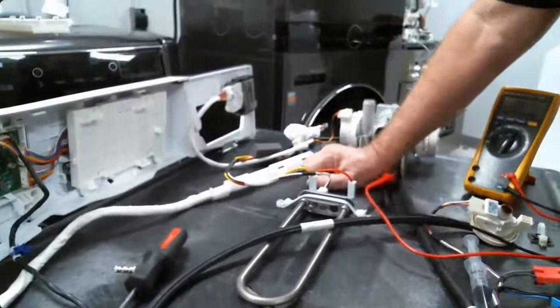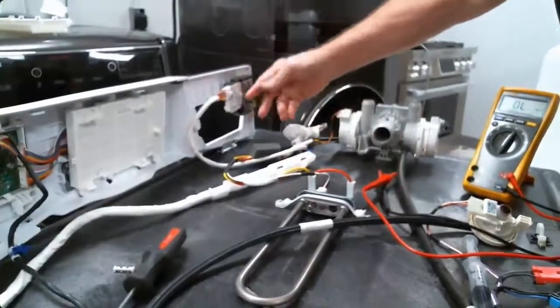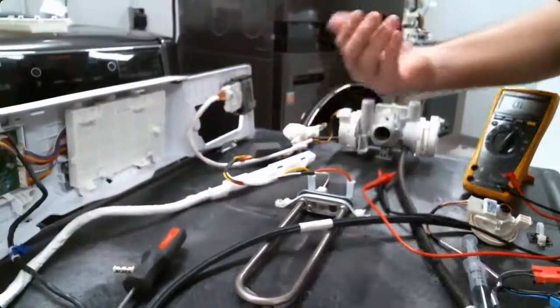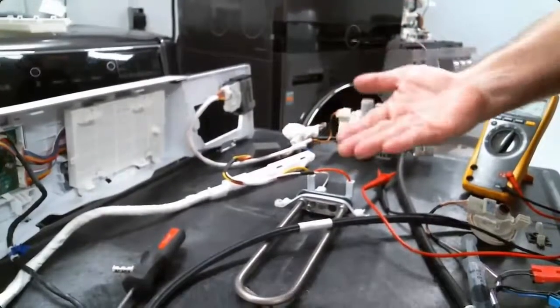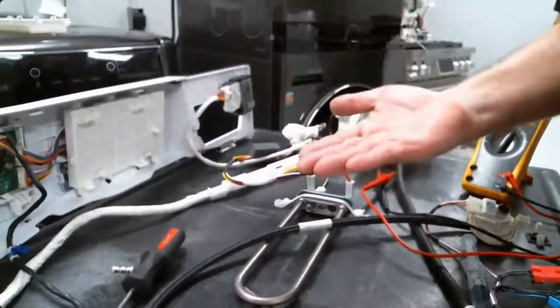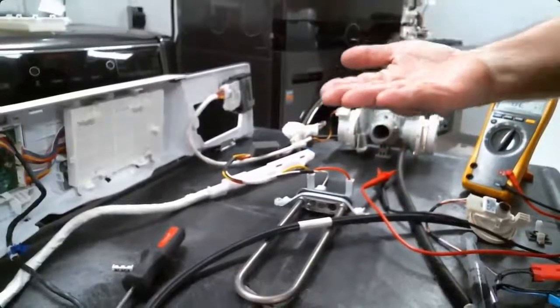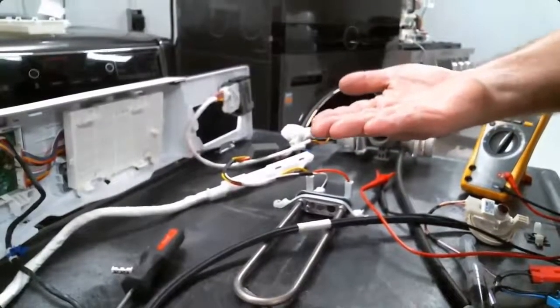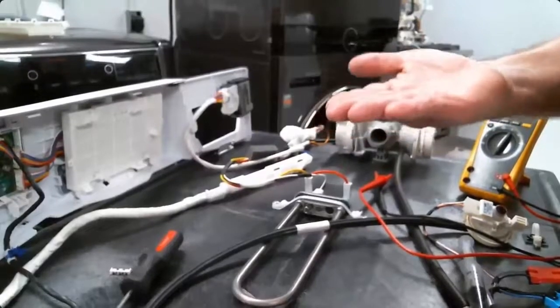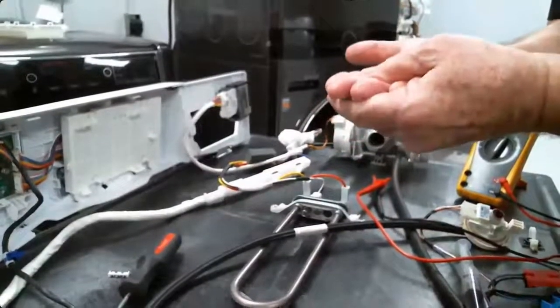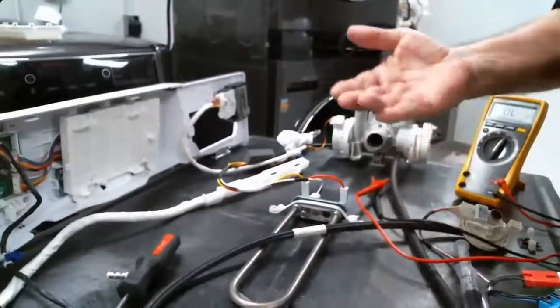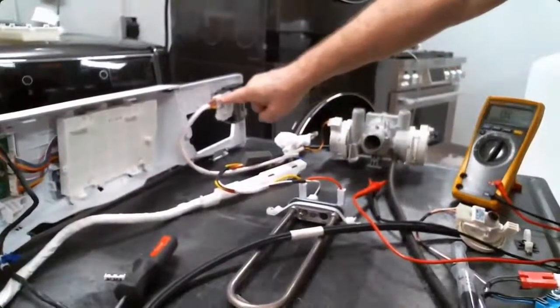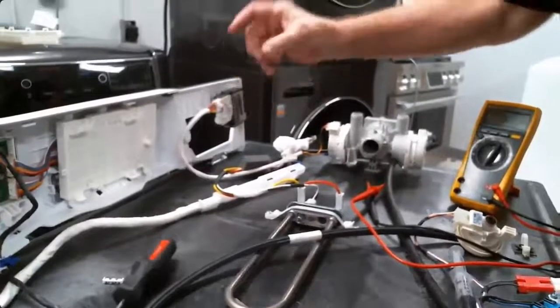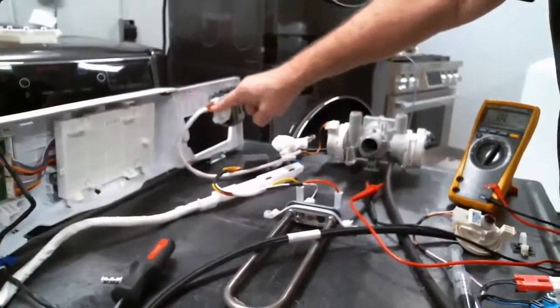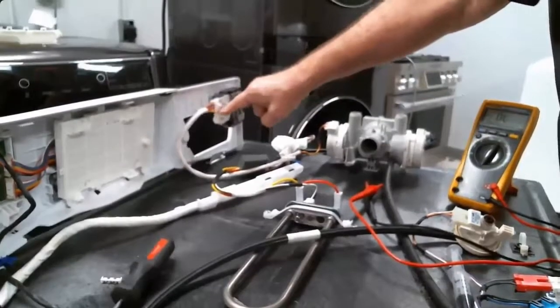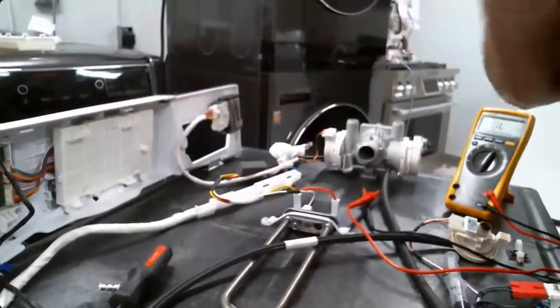Now, the heating PTC, without getting too technical, is right under a bimetal. The heat generated by that PTC causes that bimetal to slightly rise. You can let it sit there for weeks and months with that 120 volts, and it will never get any higher, because there's a limitation on how high that bimetal can rise. So to raise that bimetal all the way up in order to complete the contacts between the red and, in some cases, the black wire, in this case the yellow wire, we energize a solenoid.